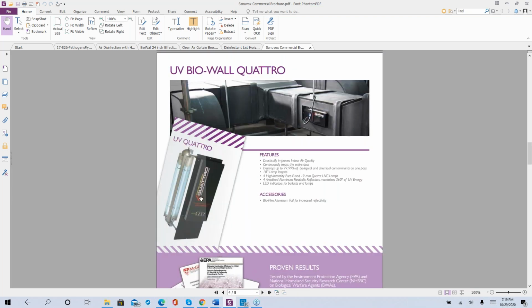So then here's the smaller Quattro. This has a built-in airflow switch. You've got to make sure that the pitot tube is pointing against the direction of your airflow. This has the 4 bulbs. These bulbs are only 18 inches long, and the entire Quattro is about 2 feet.